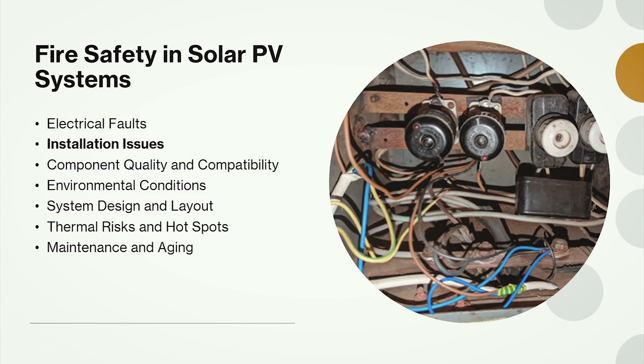poor installation, that is an issue. Often it's caused by not following designs, not following manufacturer's instructions. And a very common part would be DC cables under the PV modules wouldn't be fixed or wouldn't be installed in adequate trunking, so they would be left loose to hang around in a wind, and cables could get damaged. So securing cables is a very big part of what we can do to improve the situation.